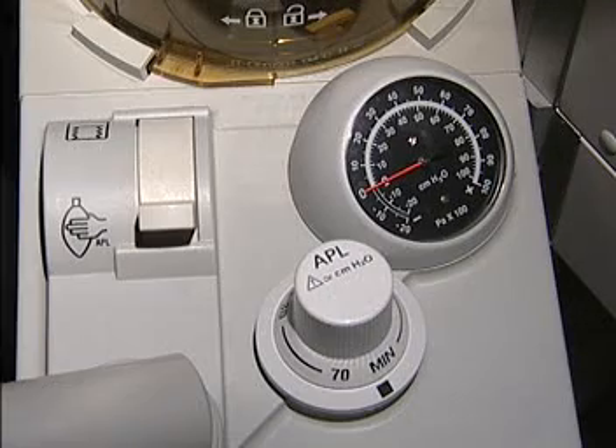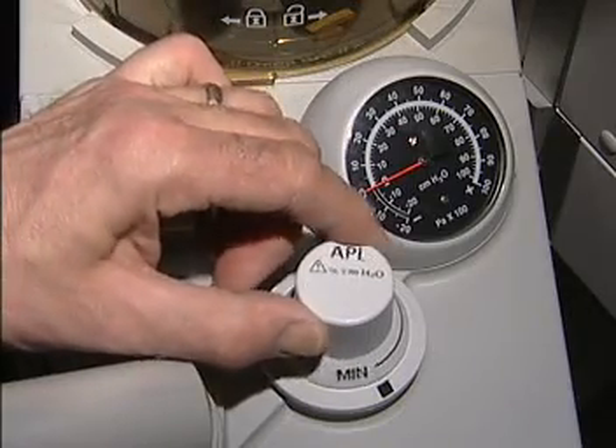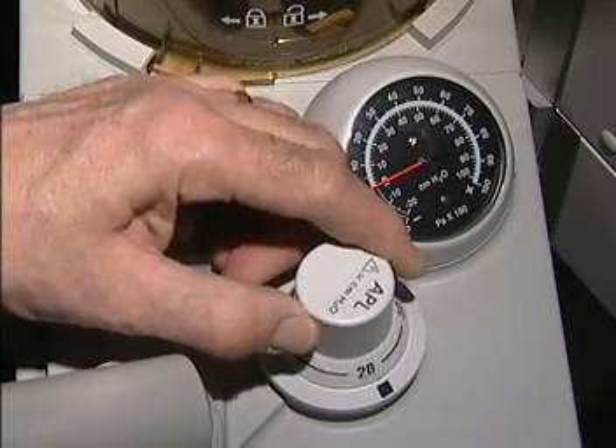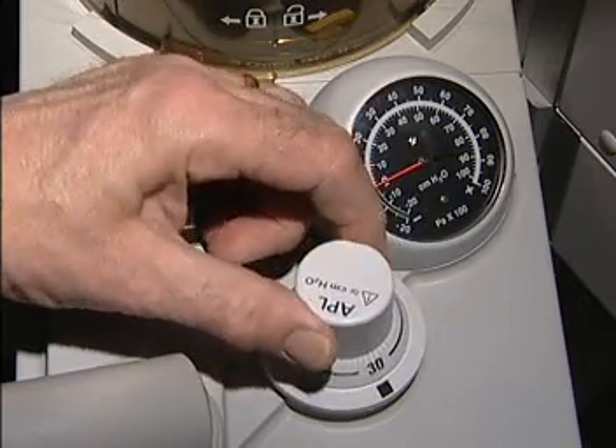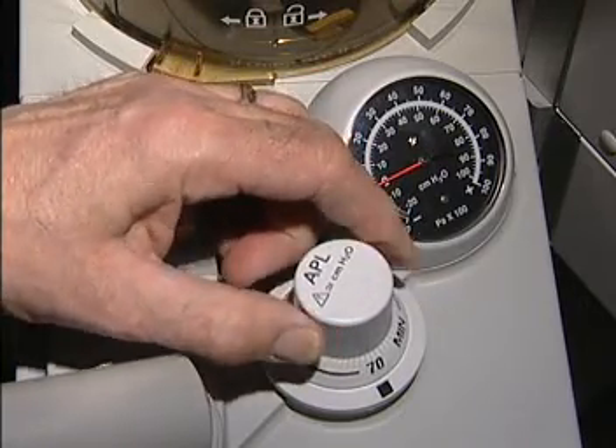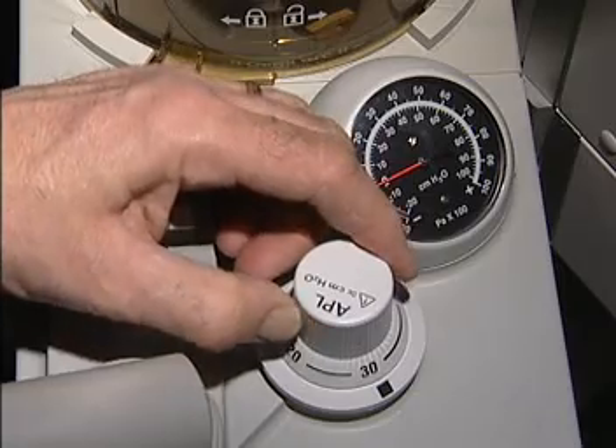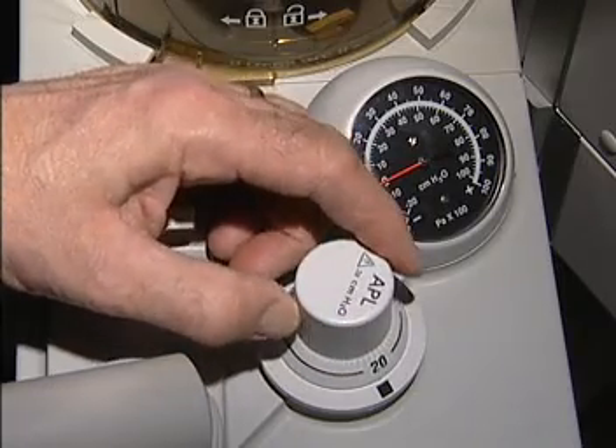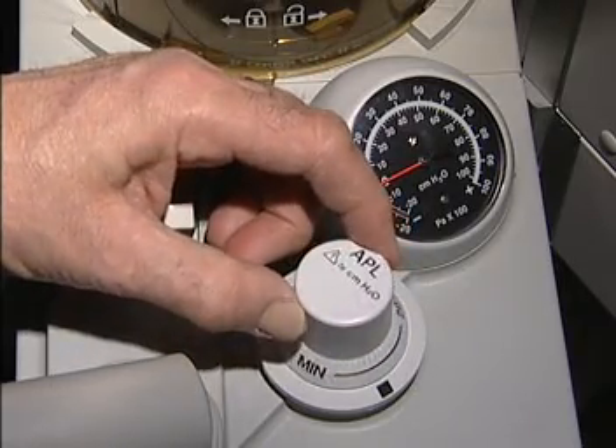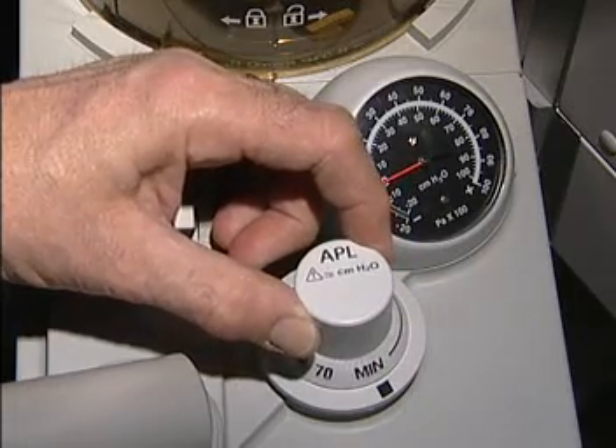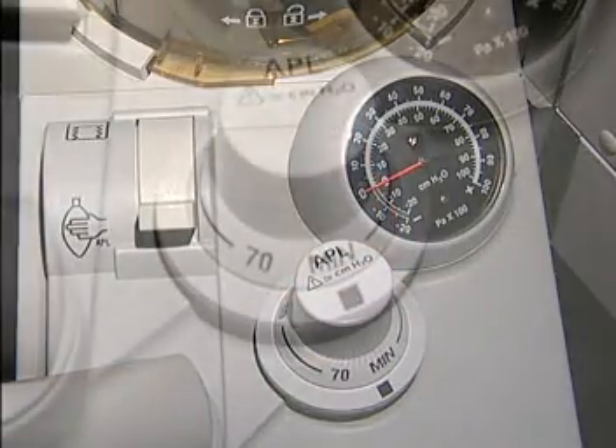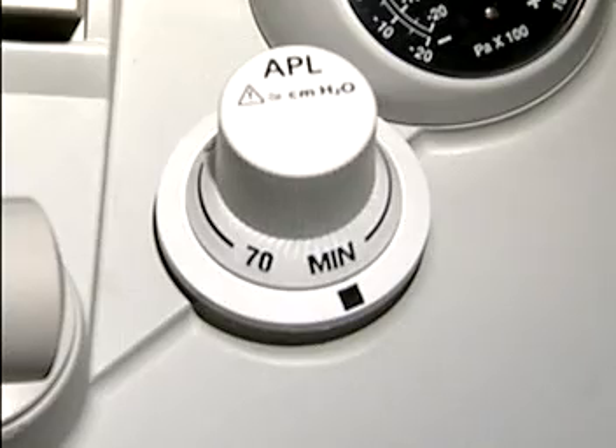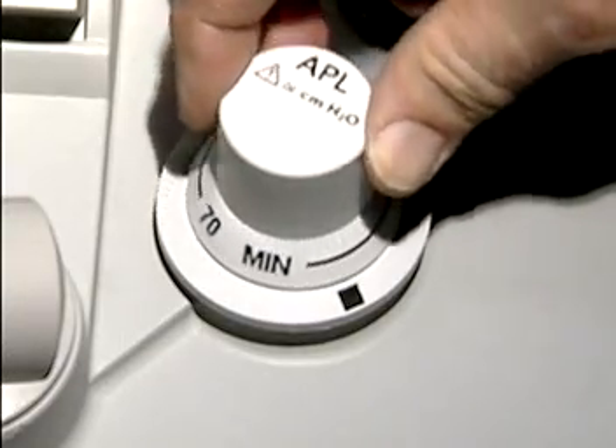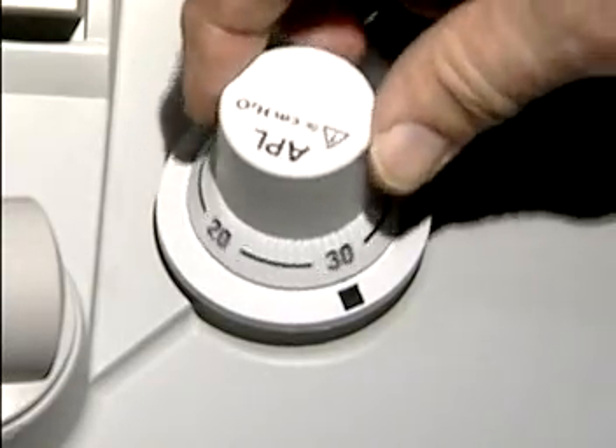With the bag vent switch in the bag position, the adjustable pressure limit valve will limit pressure in the patient circuit. The APL has been designed to allow the pressure to be adjusted from 2 to 70 centimeters of water pressure in one 360-degree turn. The adjustment is not linear, so that finer adjustments are possible at the lower end of the pressure scale. A tactile reminder will advise the operator when they reach about 30 centimeters of water pressure.